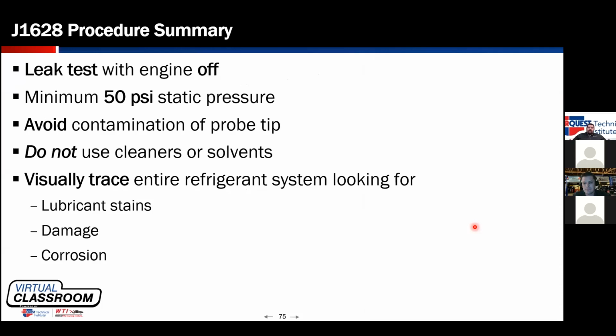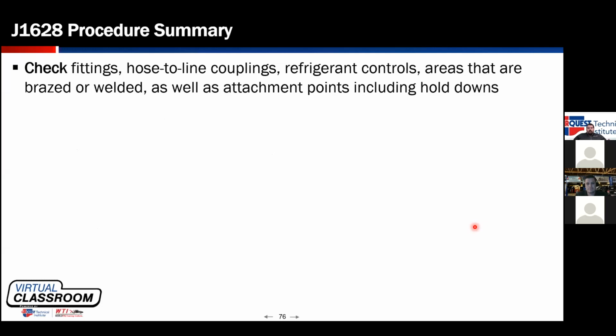Look for something obvious. If I see I've got a condenser that's bent, like the car's been in a front end impact, I'm going to go to the condenser first. Look for oil stains. Even if the system doesn't have dye in it, look for something that's heavily corroded. We're doing the mile high view at this point, looking for good places to start. We want to check all of the fittings, check every connection.